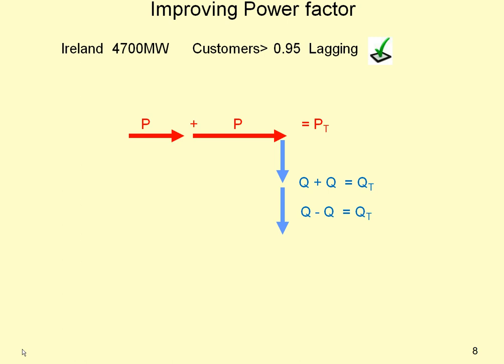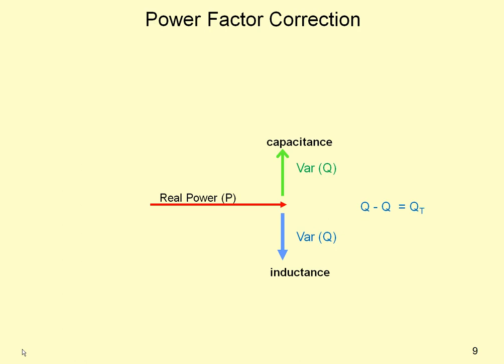We do this by being able to subtract from the reactive power. You can add to reactive power, but you can also subtract it as well. We do this by adding capacitance to the circuit. Capacitors consume reactive power, but in the exact opposite direction to the inductive reactance. Adding capacitance will reduce the reactance of the inductive power.